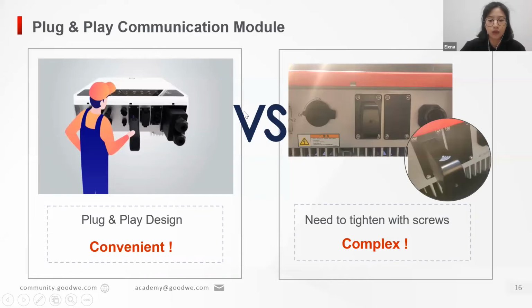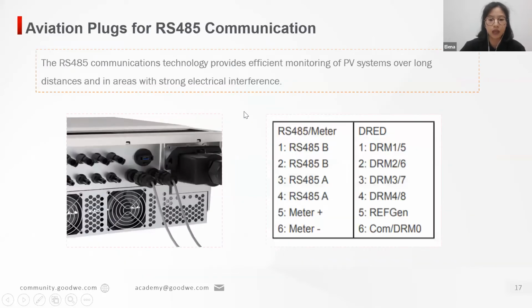For the previous design, we needed to tighten the screws, which is more complex. For another important communication type, RS485 communication, we also provide easy aviation plugs for multiple inverter applications. The RS485 communication will be used for the hand-to-hand connection and the realization of some functions. For example, export power limit with a smart meter, data collection by the data logger, and even some special functions like DRED in Australia, RCR in Germany, and remote shutdown in Europe depend on RS485 communication. So the easy installation will help installers greatly reduce the system installation time.